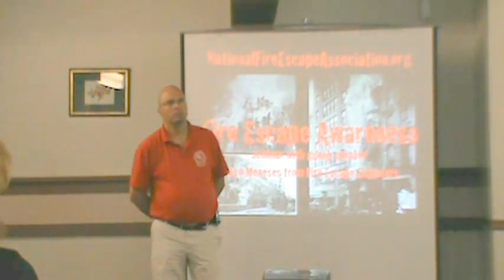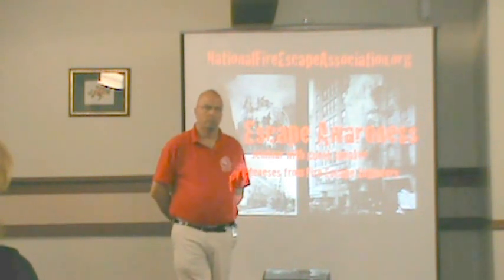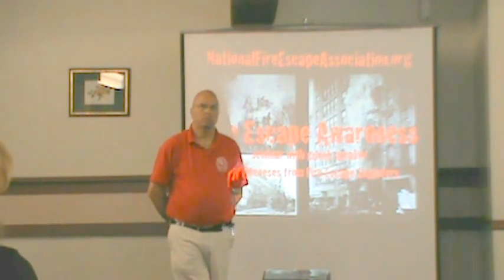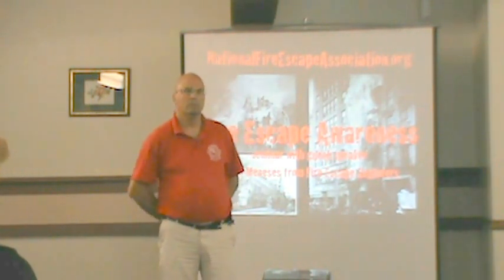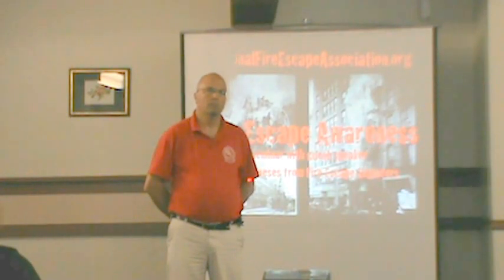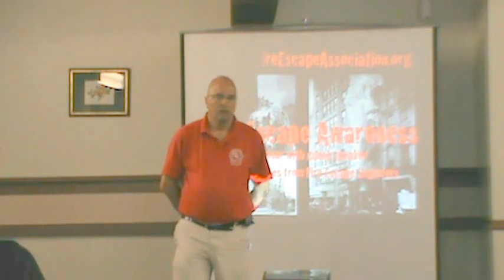Have you been told, per Regulation 4, or even just the state of California, state fire marshal or anything, if I'm going out and inspecting a fire escape assembly, which includes some sort of drop ladder assembly, and I'm looking at the fire escape and I say, in my opinion, it looks okay, but the counterweighted weight box is completely rotted out and needs to be replaced, is that a permit situation? Yes. Because anytime I'm replacing parts on it or altering it or repairing it in any way.